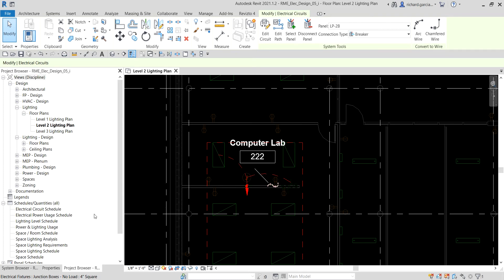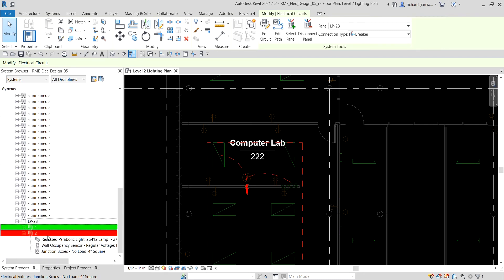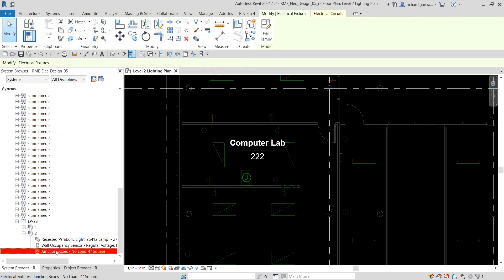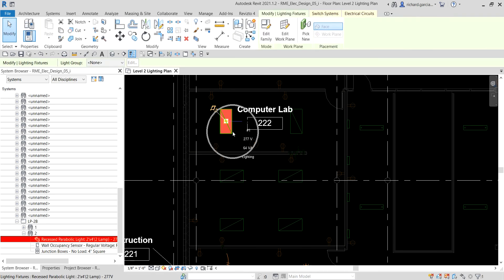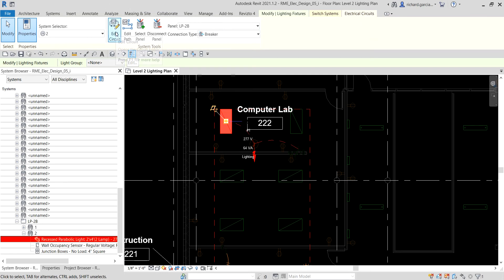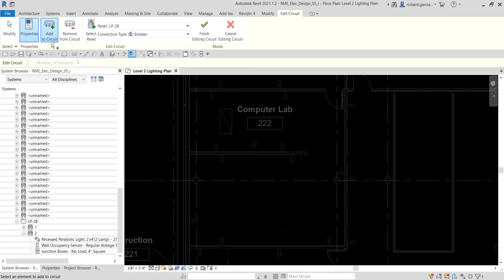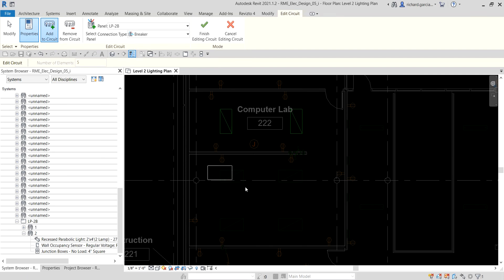If I go to the system browser, I can now see that the junction box has been added to that circuit. To finalize, I'll select one of the lighting fixtures that is part of circuit number two, go to Electrical Circuits, select Edit Circuit, and add all the remaining elements: this lighting fixture, the other sensor, and these four lighting fixtures. Then I select Finish — and that's it.